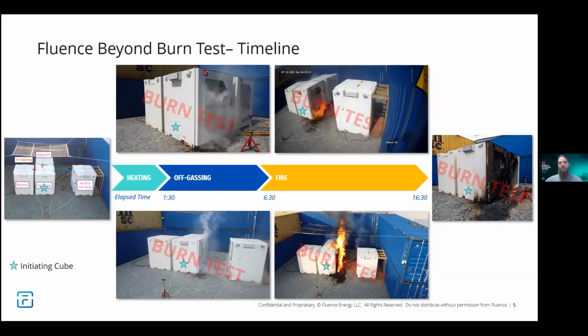Throughout the test we had the off-gassing — you see that white gas really indicative of a lot of battery fires, coming out of the cube at the bottom and through the door. At the top right, you can see the moment of ignition, most likely reaching auto-ignition temperatures of some of the gases or materials around that bottom left-hand corner.